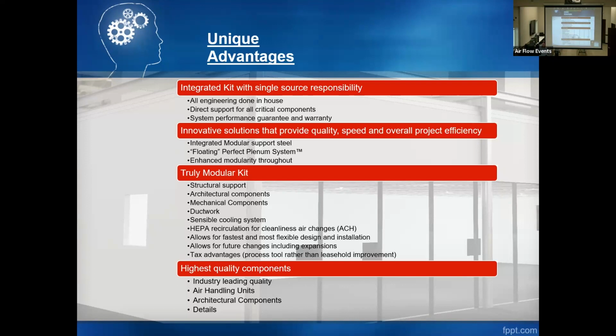If you don't have ceiling height, we try to put the unit indoors next to the room. We've done them outdoors. Again, leakage is an enemy in these types of environments. One pinhole leak in a minus 40 dew point space, you're going to be chasing that problem. So yes, we do ductwork, we do the HEPA recirculation, air changes an hour.